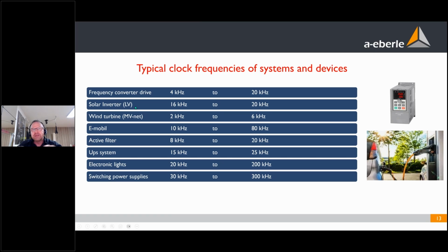Solar inverters, which we install at households in low voltage grids, typically make disturbances at 16 or 18 kilohertz. So why 16, 18 kilohertz? We can hear noise and disturbances up to 15 kilohertz. And they put the sampling frequency a little bit higher than the frequency we can hear, because we install a lot of solar inverters in households. If the sampling frequency were, for example, 9 kilohertz, there's a big risk that all the people can hear this beeping noise of 9 kilohertz in their household equipment.